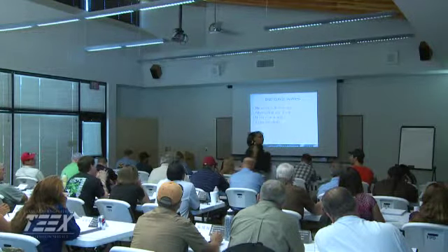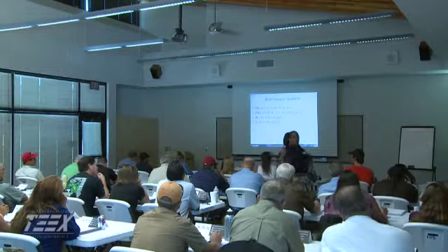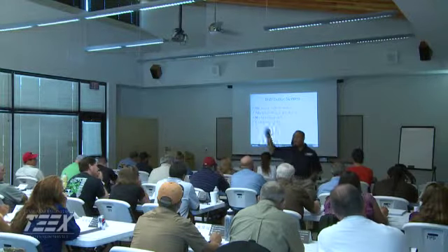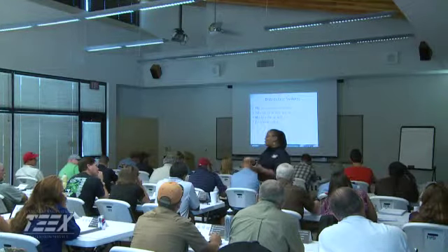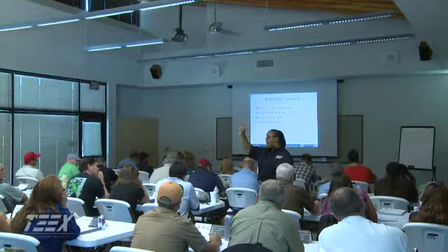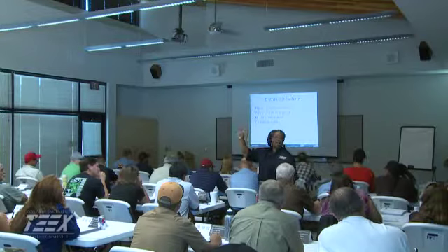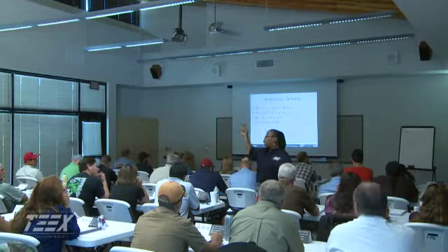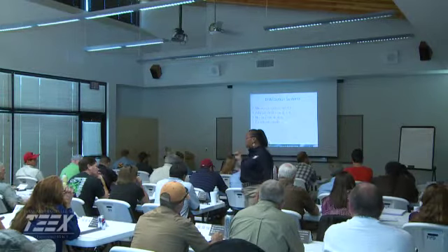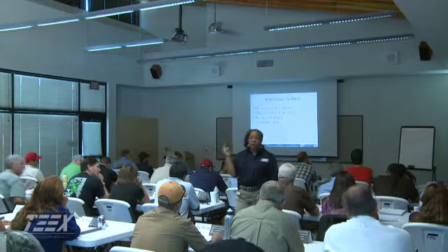That's one critical safeguard. What's another critical safeguard? Maintaining adequate pressure. And remember, adequate pressure, that first number that you all remember is 25. Never in any circumstance, even in emergency condition, should it drop below 20 psi. Very good.